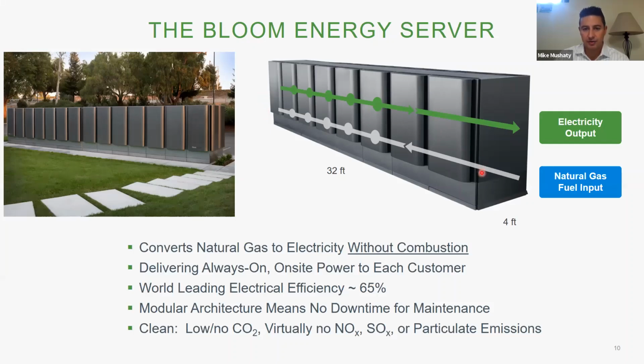These 8 modules serve different purposes. The first module is what we call our input-output module. That's where the electricity that's generated by the fuel cells is inverted from DC power to AC power and delivered to your facility. The second module is my gas module. That's where I take in the natural gas feed, knock down the pressure, and clean up the natural gas a little bit, removing some of the constituents that aren't methane that the natural gas company injects into the pipeline, before the natural gas goes to the power modules for electricity production.